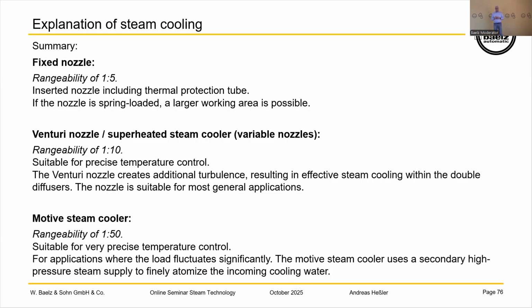And the biggest one, or the best one, is the motive steam cooler. We have a rangeability of the water of 1 to 50. Here we have the motive steam to vaporize the water, and at the outlet we have more like a fog instead of water droplets. So we have much more area where the steam can go through the water and vaporize it. So we have a very small distance to the temperature sensor. We can cool down very low, to near the saturated steam temperature.